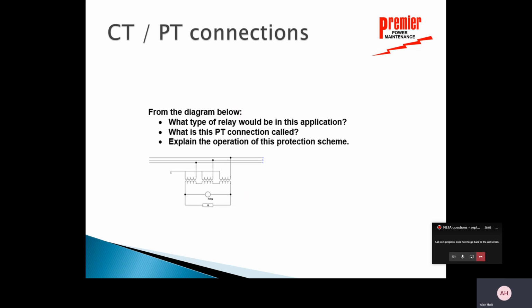Well, one thing we've got to look at is that we've got these PTs connected to the line. So here's the line, and I have PTs connected, and they're connected Y on the source side. Oh, wow, it's called a broken delta. I've got a delta connected here, but it's not closed here, so that's called a broken delta. So one thing I have to understand is, why would somebody do something like this?